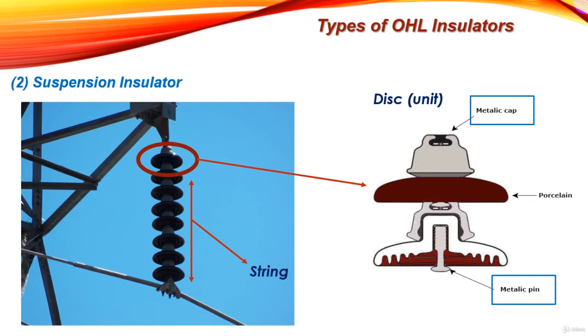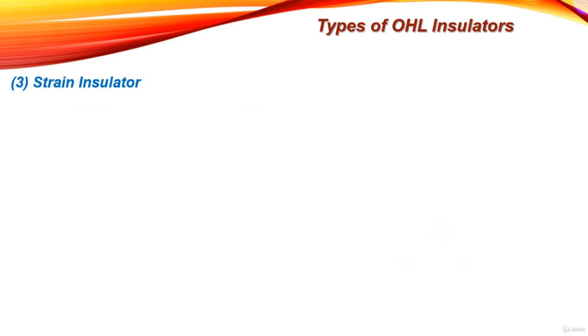A string of any number of units can be built according to the line operating voltage. As the line operating voltage increases, we can use a greater number of units to withstand the voltage of the conductor. This is the key advantage of the suspension insulator. The third type of overhead line insulator is called the strain insulator.